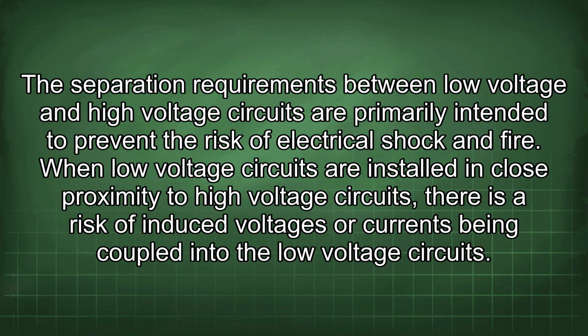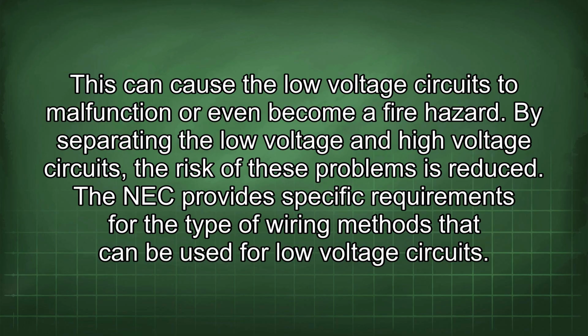The separation requirements between low voltage and high voltage circuits are primarily intended to prevent the risk of electrical shock and fire. When low voltage circuits are installed in close proximity to high voltage circuits, there is a risk of induced voltages or currents being coupled into the low voltage circuits. This can cause the low voltage circuits to malfunction or even become a fire hazard. By separating the low voltage and high voltage circuits, the risk of these problems is reduced.